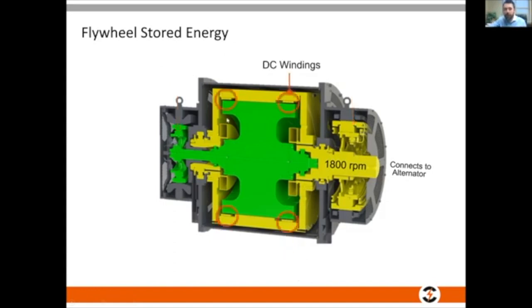In case of a mains failure, I inject a DC current into these windings. Simply what I'm doing is creating a magnetic field. And in layman's terms, I'm creating a magnet. And as I create a magnet on this yellow, so it's 1800 RPM winding, it is effectively braking the inner drum that's spinning much faster. So as that yellow device spins, it pulls on the pole of this inner device, and every time it passes a pole, the magnet will continue to spin. So ultimately, that magnet means that my 1800 RPM will spin indefinitely, or until at least this flywheel slows down below 1800 RPM. So it's just by virtue of a magnet that we're pulling the energy from the flywheel to ensure that the 1800 RPM doesn't slow down.